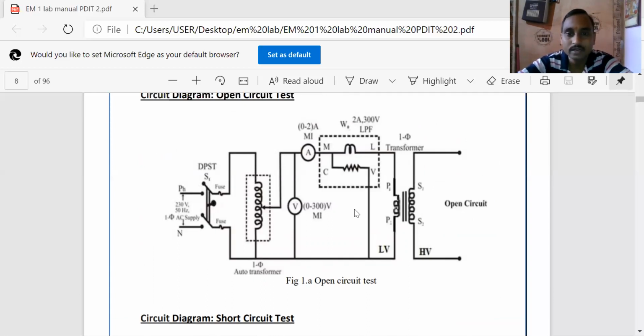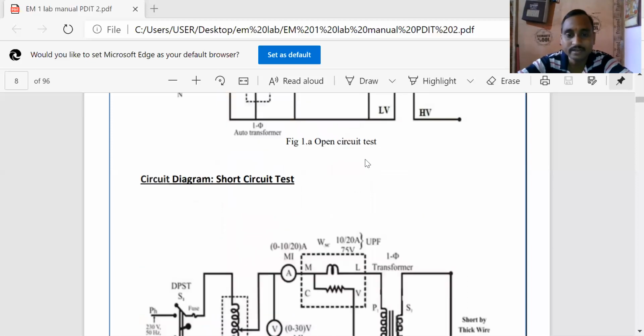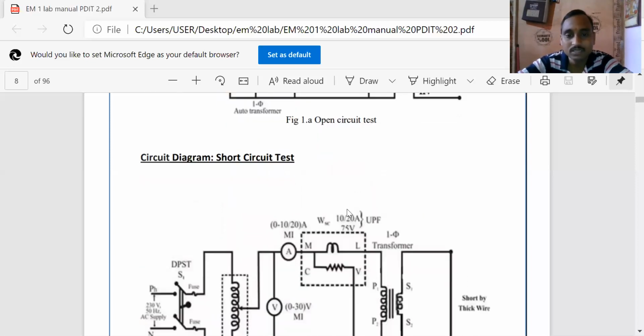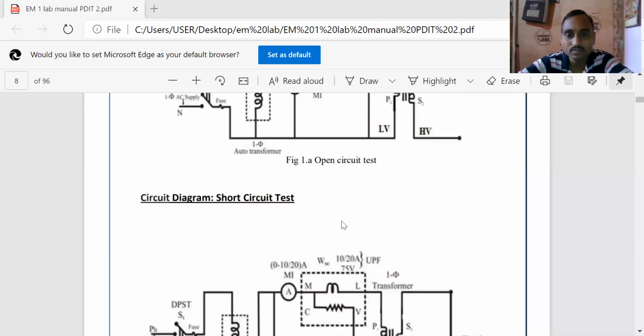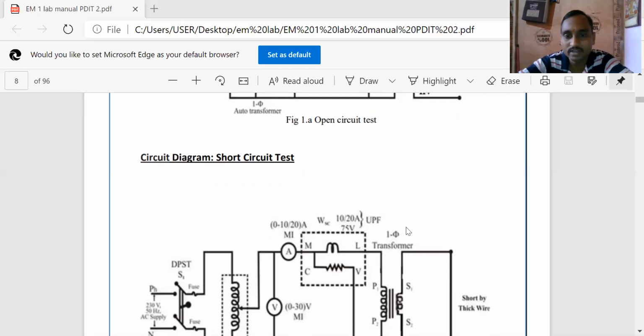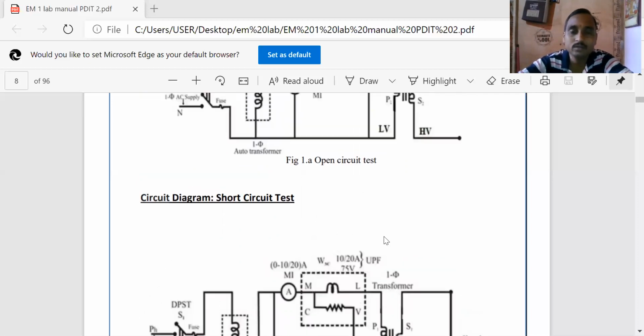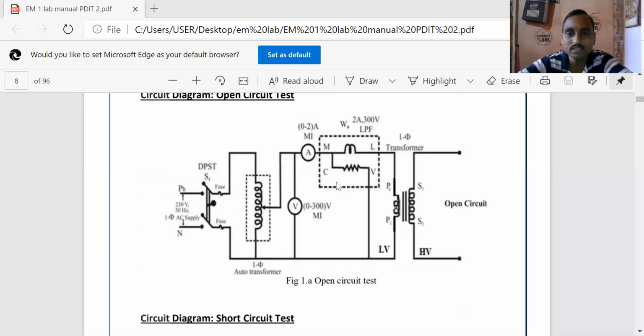Say 300 volt. And current range means what is the current range of the wattmeter, either 2 amps or 10 amps. So depending upon that, you need to take the current range of the wattmeter. And power factor: if it is unity power factor, you take it as 1. And if it is a low power factor meter, it is mentioned on the wattmeter range, so you take that particular power factor.